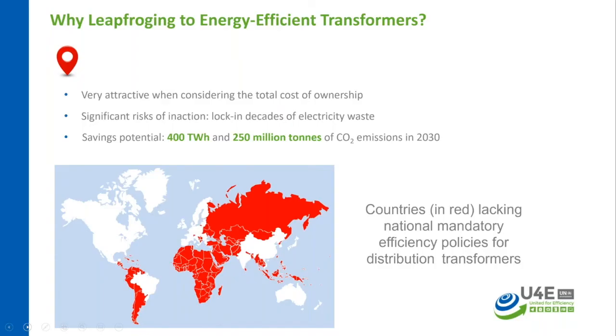So while leapfrogging of transformer energy efficiency is needed, although these transformers are generally procured on a life cycle cost basis by the utility, in most cases there is an opportunity to improve the performance over the MEPS. Like you have seen in an earlier presentation, the MEPS sets the bare minimum, but the labels encourage a higher efficiency market. In the same way, if the MEPS establishes the minimum baseline for the procurement or the energy consumption in transformers, the life cycle cost-based purchase adds further energy efficiency and gives you the right solution for your system.